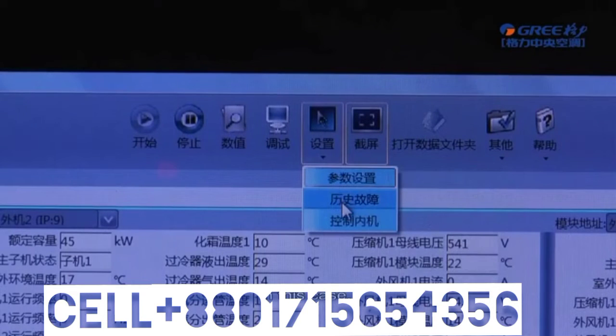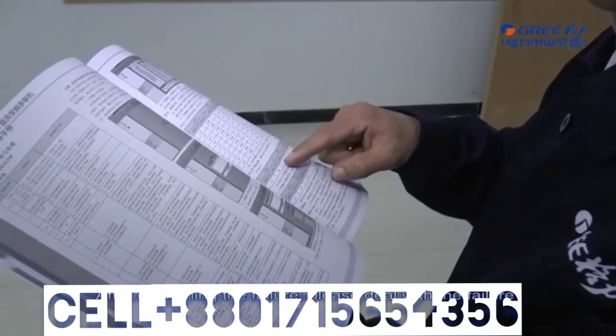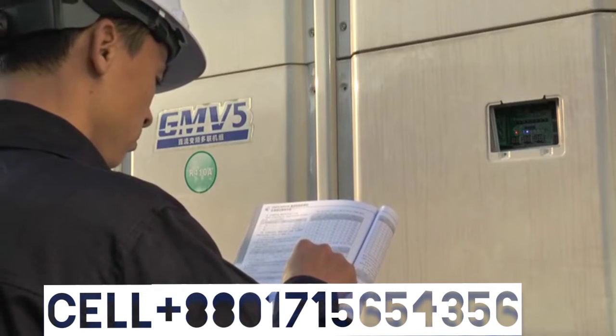The other is failure log inquiry. In this case, the failure has been eliminated and inquiry will be done through debugging software or wired controller. 4. Malfunction elimination. After confirming the failure, please deal with the failure according to the troubleshooting of installation, debugging, and maintenance manual. 5. Confirmation with the user. After eliminating the failure, please explain the cause and operation precautions to the user and make the maintenance record.